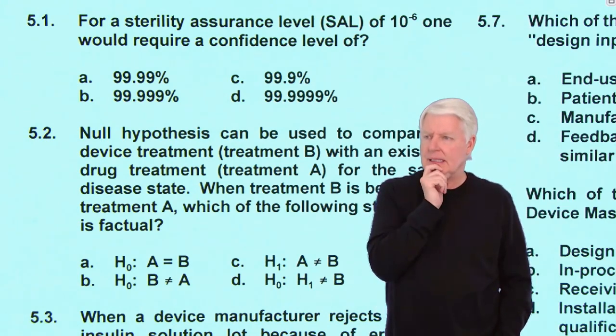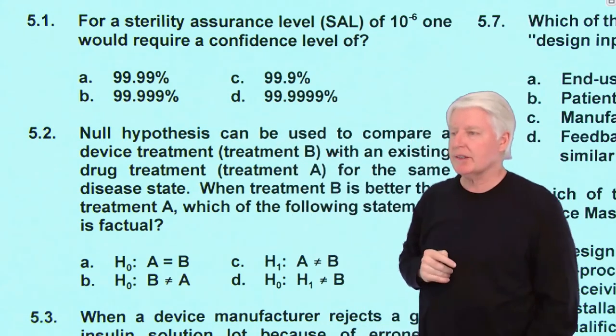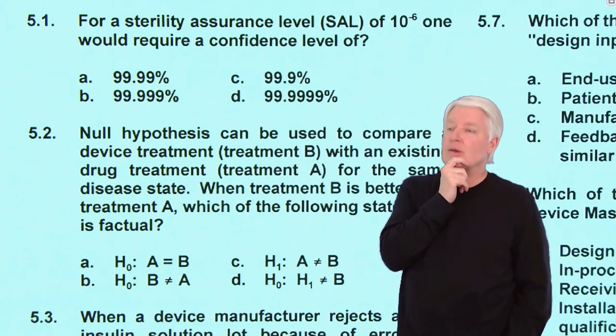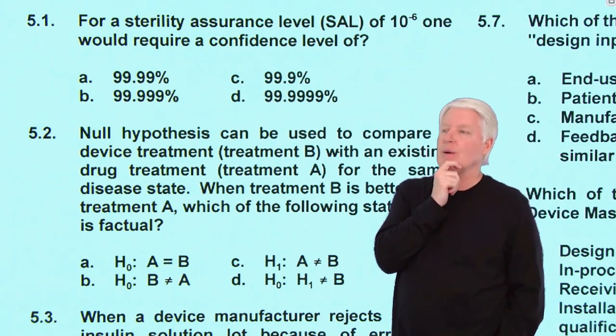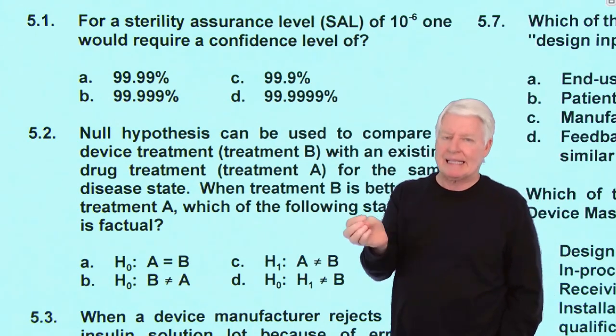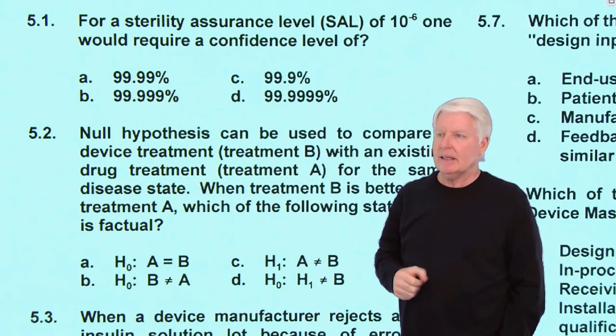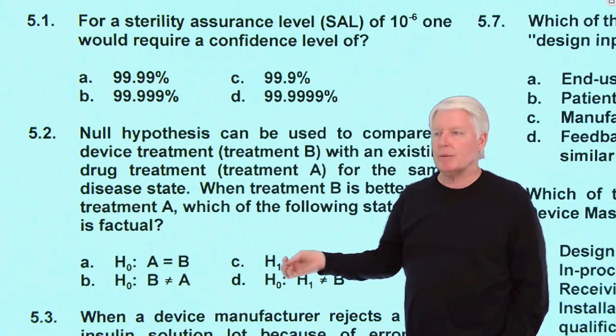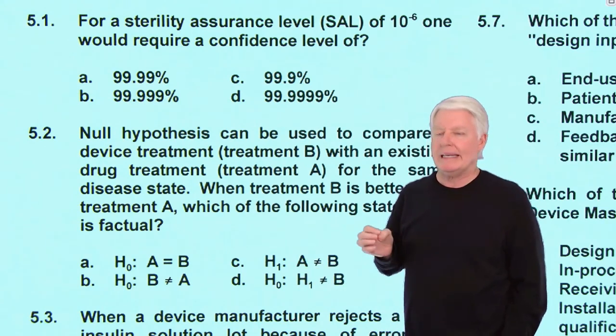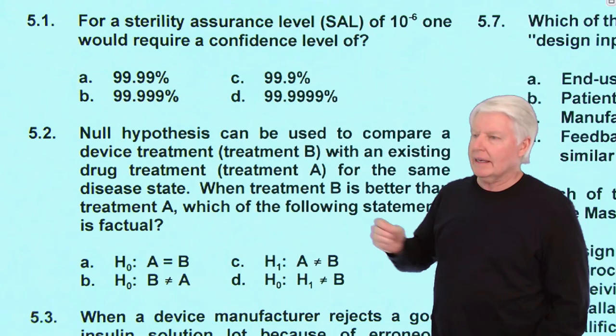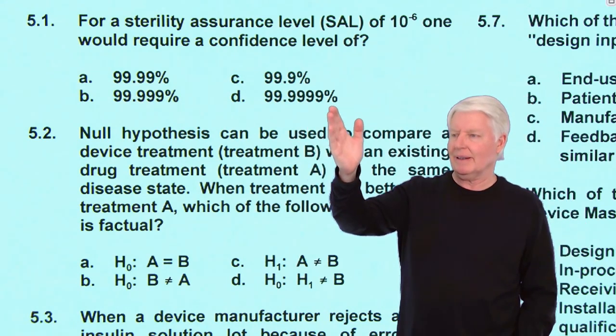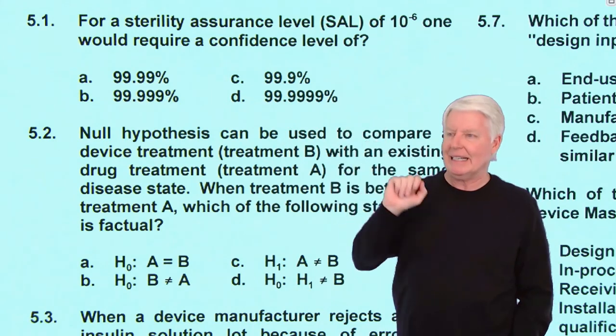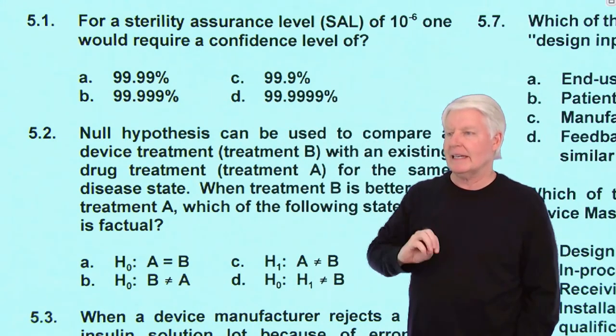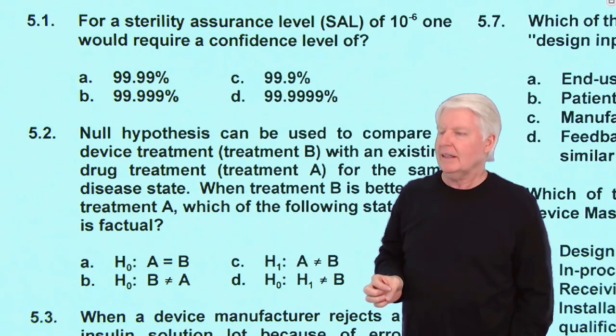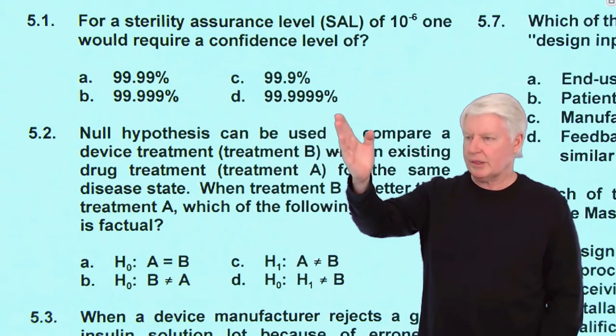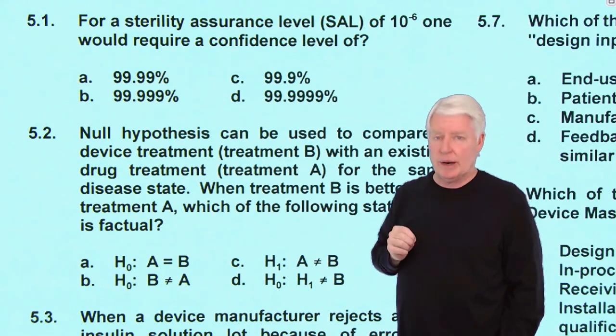Okay, and that would be acceptable, I guess, for this company that we're talking about. So that's what it means. And for 10 to the negative 6, if you want the confidence level, you subtract the SAL from 100%. So if you take 1 part per million and subtract it from 100%, you're going to end up with 99.9999%. There it is, 99 point, then there's 4 nines. That's 0.999999, which is what it will be if you take 10 to the negative 6 and subtract it from 1, and then you convert it to a percentage. So D is the correct answer for 1.